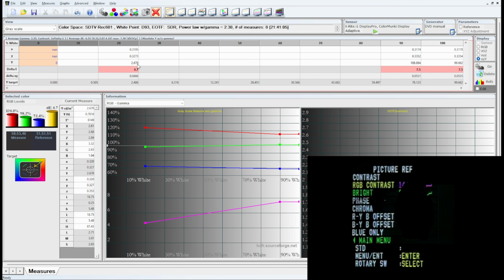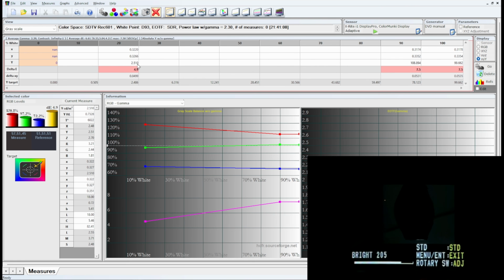I'm gonna lower the brightness by just 1 and see if that gets us there. The problem is at 20 nits, these adjustments just going down by 1, you can see how much it affected it. So the changes on these are a lot more drastic. And on a consumer set, you're gonna have even wider gaps. So let's say your contrast is set to 50 out of 100. Usually on consumer CRTs, you get 0 to 100 for your settings, so you set it to the default of 50, and you go down by 1 and you lose like 5 nits just from going from 50 to 49. So the PVM controls are much more precise. Keep that in mind. So 2.4 is pretty darn good.